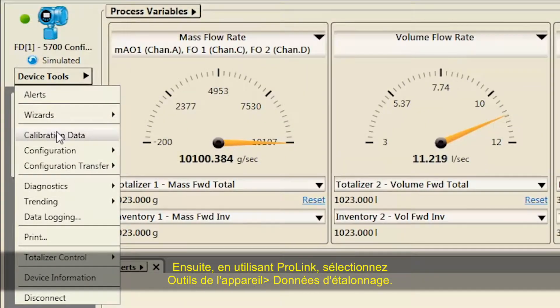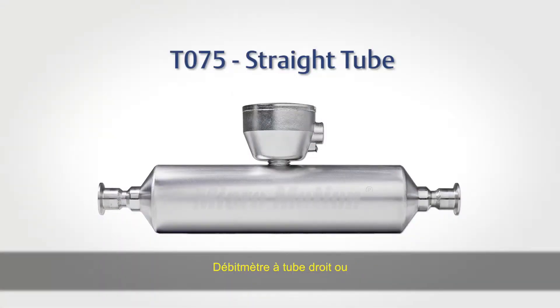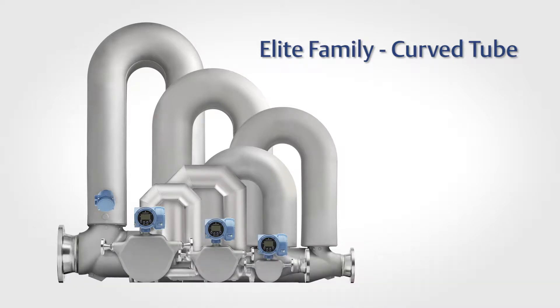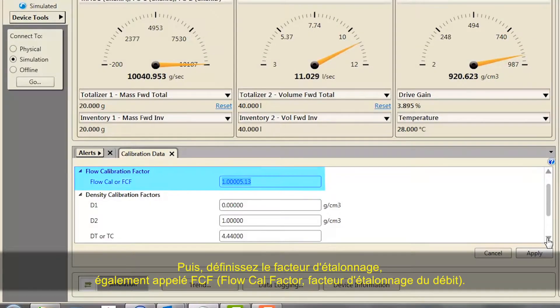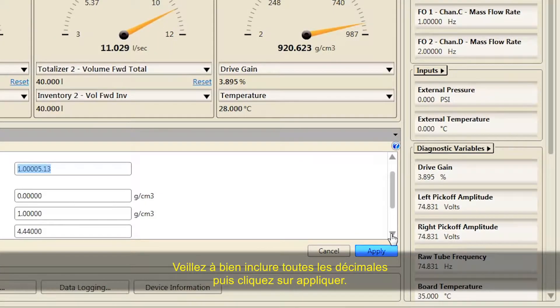Second, using ProLink, select Device Tools > Calibration Data. Third, confirm your sensor type — straight tube, straight tube meter, or curved tube (which would be all sensors except a straight tube meter). Fourth, set the flow calibration factor, also known as FCF or flow cal factor. Be sure to include all decimal points and then click Apply.